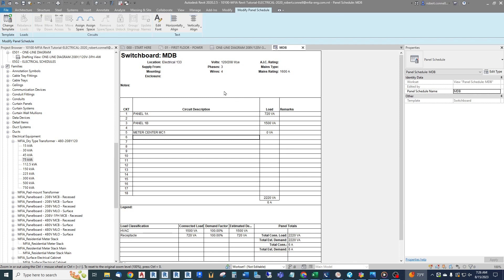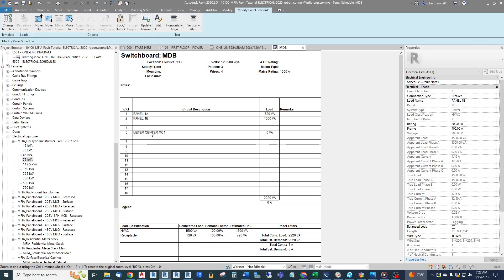That's the long and short of how to connect panels together for your distribution system and how panel schedules work. You can also reorder items in the schedule — if you don't want gaps, you can move the meter center up or down using Move to pick a new spot, reordering as needed. This is a customized template for switchboards in our project template — it only shows the load, not the circuit breaker or individual loads, because we let our one-line diagram dictate the feed rather than the schedule dictating the breaker or fuse size. It does add up all the loads for you at the bottom. That's it for now until the next one.